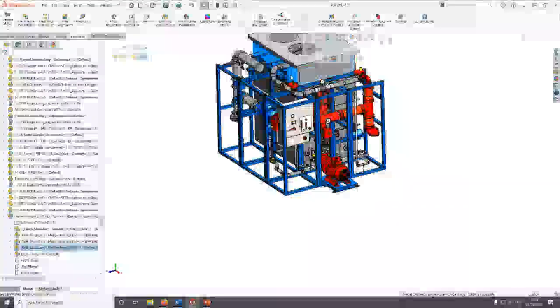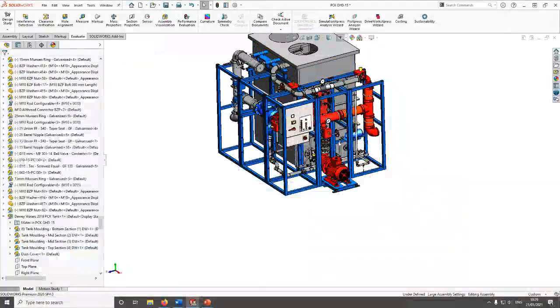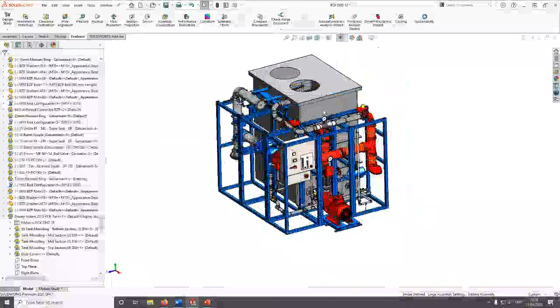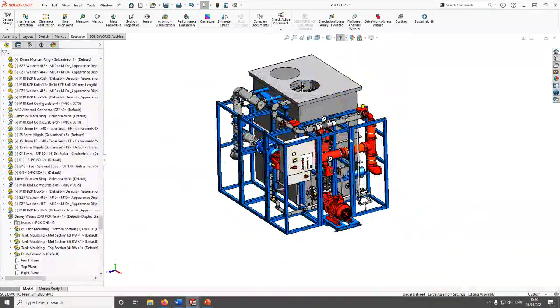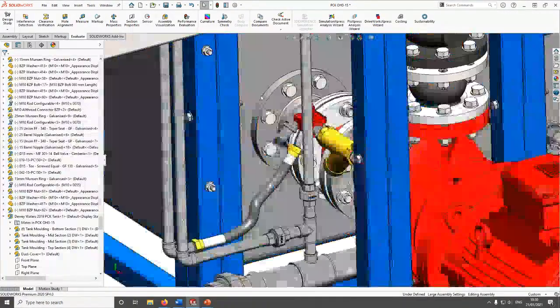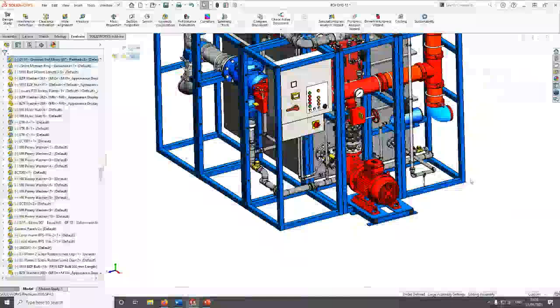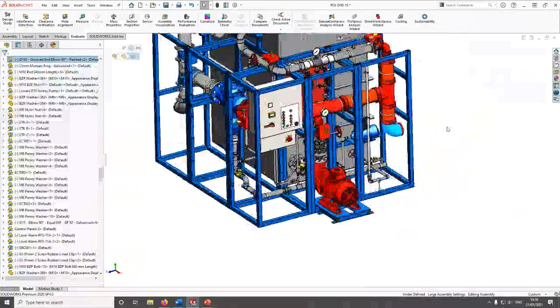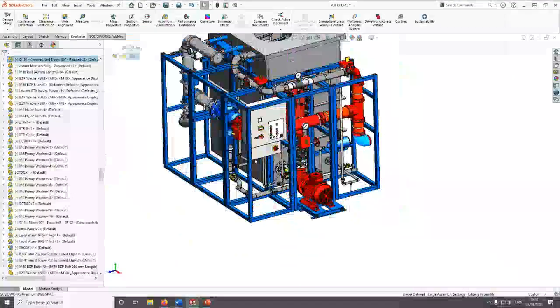So our fire pump will start, and that will then suck water out of this. You can call it a tank if you like, but we call it an RPZ. No, we don't. We call it an AVC. Got my acronyms mixed up there. We call it an AVC, an anti-vacuum chamber, because this tank isn't really there as a stored water supply. It's there to protect the fire pump, like a break tank, if you like, from the town main. So that will start sucking water out of the bottom of the AVC, up through here, and then along and out through this elbow into the sprinkler system. It's just like a normal kind of pump and tank solution, other than the fact that the pump is drawing from this much smaller tank, which we call an AVC.